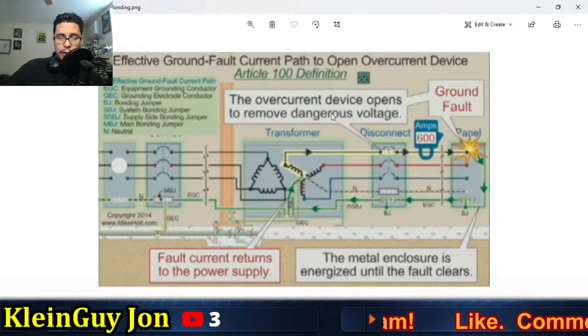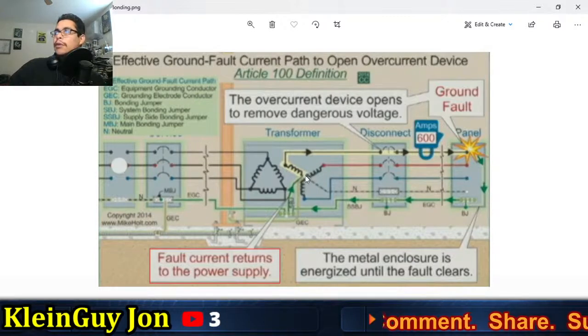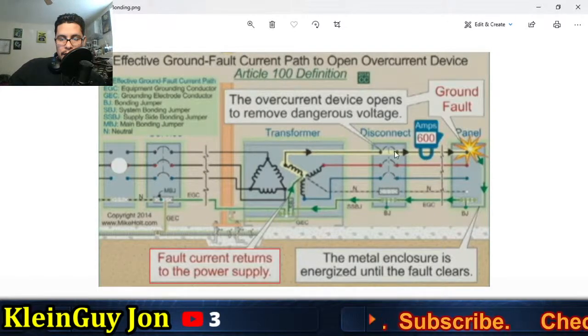So in this case, in this ground fault here, as you can see, it says the overcurrent device opens to remove dangerous voltage. Ground fault. So let's say one of the hot legs, pow, you've got everything properly grounded. You have an effective ground fault current path. How it works: there's a fault at the panel. Where do electrons go? They go through the metal framing, to the bonding jumper, to the equipment grounding conductor, through the bonding jumper, then off the supply side, then to the system bonding jumper here, and then back to the transformer, back to the source. What happens then? It'll sense there's a fault, okay, and the breaker will trip.